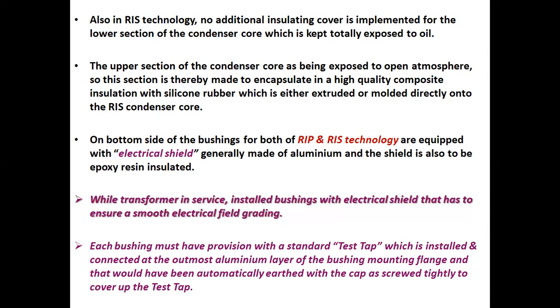The upper section of the condenser core, being exposed to open atmosphere, is encapsulated in a high quality composite insulation with silicone rubber, which is either extruded or molded directly onto the RIS condenser core. The bottom side of the bushing for both RIP and RIS technology is equipped with an electrical shield, generally made of aluminum, and the shield is also epoxy resin insulated.